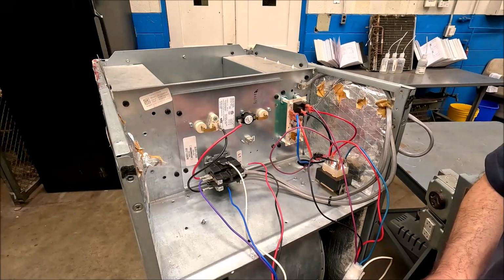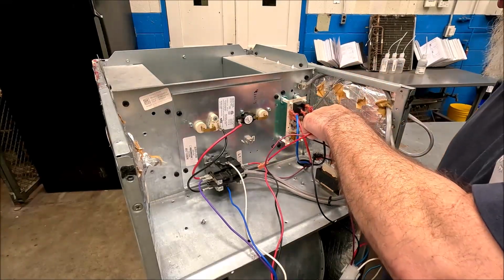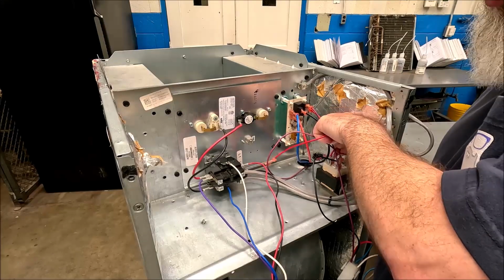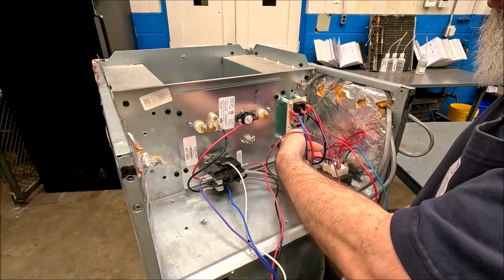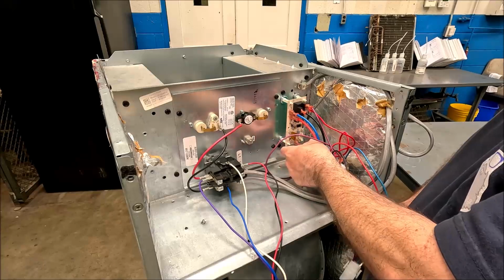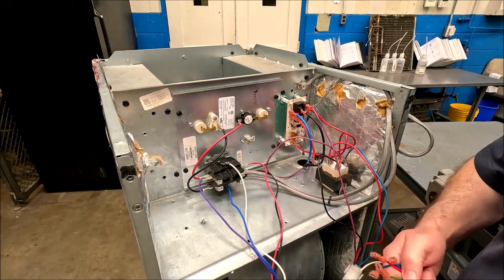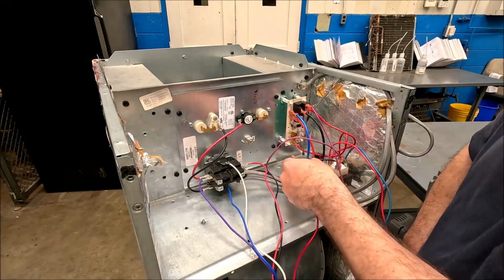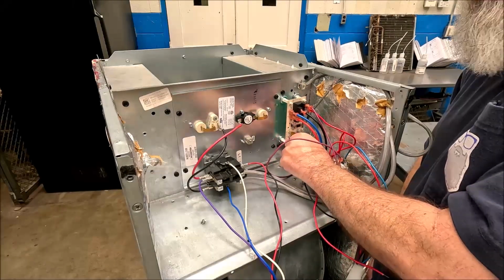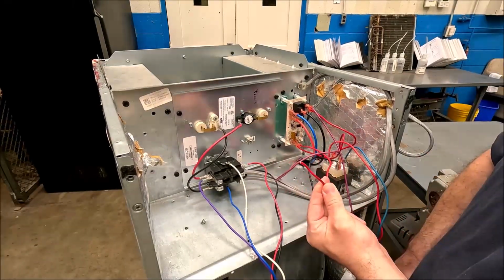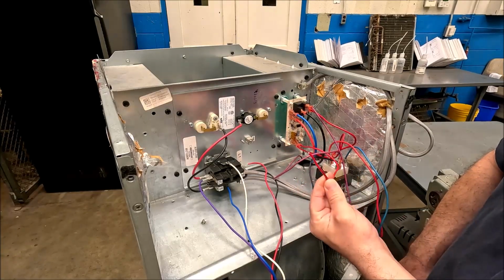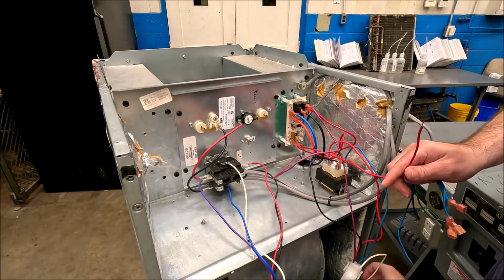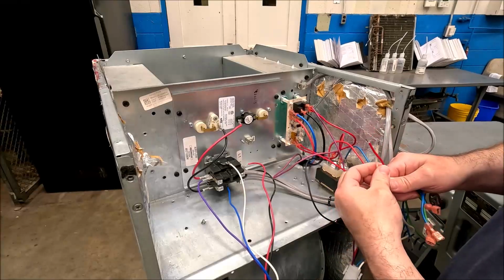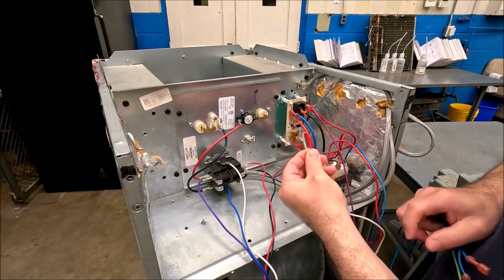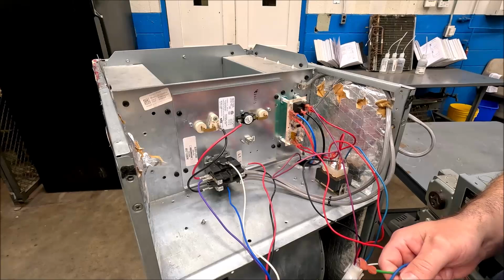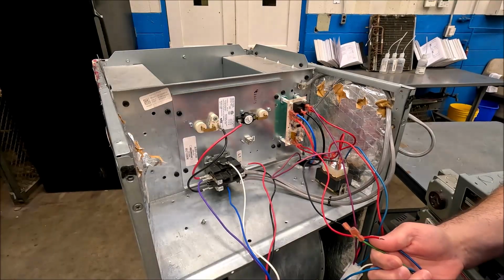So I've got a low voltage here. I got 24 volts off of the transformer, and we're going to go into the transformer R of the board. It goes through the fuse. We've done the flow on that, and then it hits the regular R. And the regular R is where I just get a bare wire, I'm going to wire nut on the end, so I'm starting to build my low voltage connections. I've got a red and a white wire that would be my air handler wire nut connections. I've also got a transformer common.